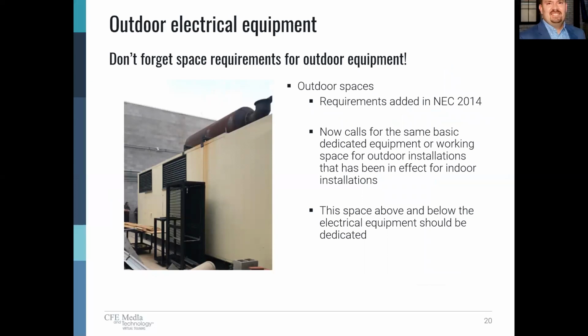So we got to make sure that we don't forget about our outside electrical equipment installations. Back in 2014, the NEC added some specific language that requires that electrical equipment be provided with the same basic dedicated equipment and working space for outdoor installations that we would have for the similar electrical installation indoors. The same is true for the dedicated space above and below that equipment. It's important that we take this into account as we coordinate with civil engineers on a project. There's a lot of entities that are vying for real estate on a project, and we got to make sure that we speak up early and often to allocate the spaces we need for our electrical equipment.